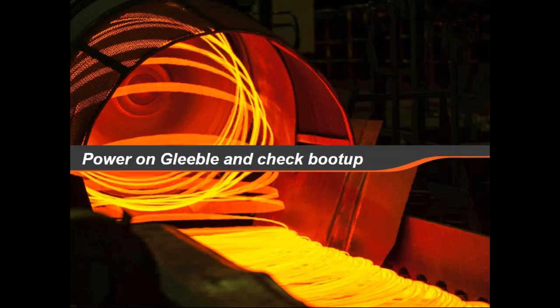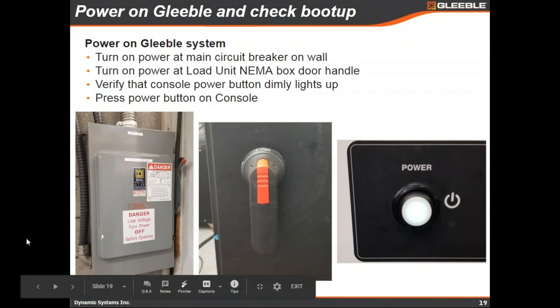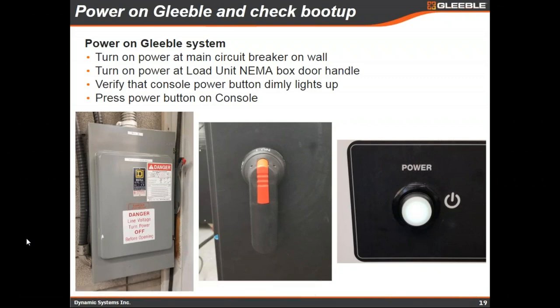Next we'll move to actually powering the Gleeble on and checking the boot-up sequence. Many of you will be familiar with this. Make sure whatever circuit breaker on the wall goes to your Gleeble is switched on, then turn on power at the load unit handle shown in the middle. The power button should dimly illuminate — assuming it does, you can press the power button to power on your Gleeble.